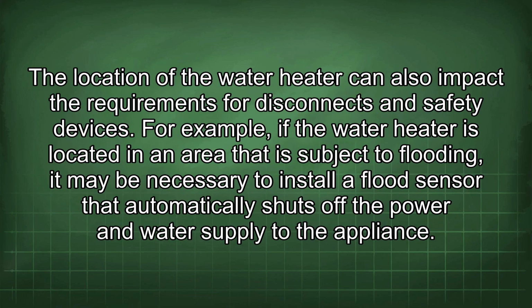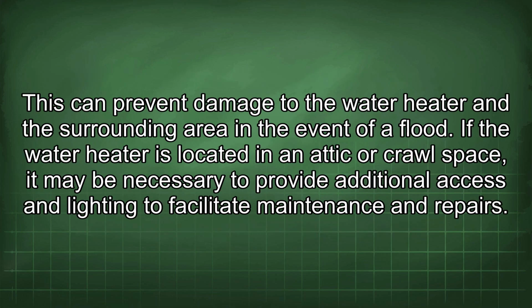The location of the water heater can also impact the requirements for disconnects and safety devices. For example, if the water heater is located in an area that is subject to flooding, it may be necessary to install a flood sensor that automatically shuts off the power and water supply to the appliance. This can prevent damage to the water heater and the surrounding area in the event of a flood.